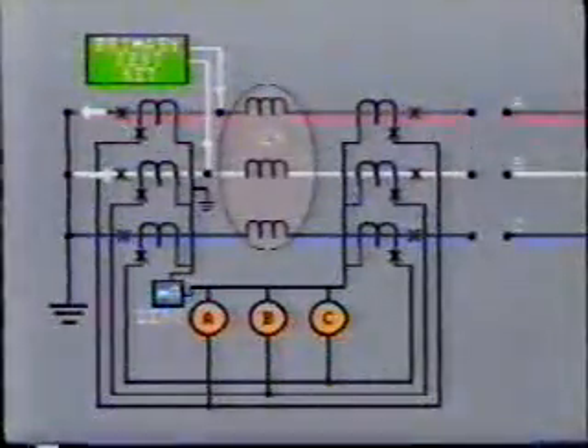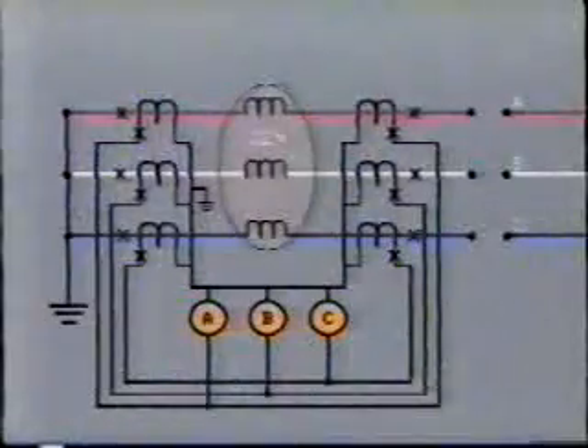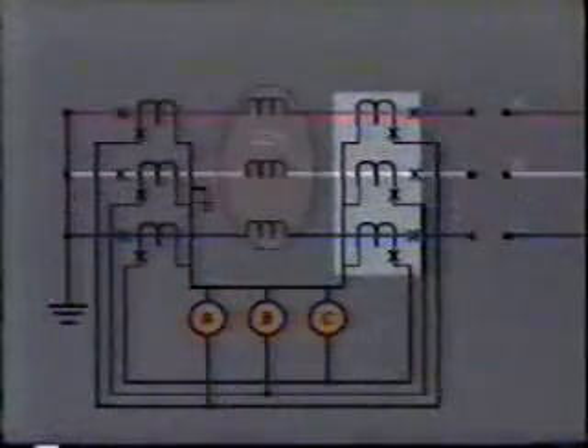To check the balance of these relays, it is necessary to circulate test current between two phases at a time. Remember, the windings are permanently connected together here. This is similar to the test that we performed earlier on the overcurrent relay. A similar set of tests would now be performed on the CTs at the other side of the generator. On the balance test, we would have to place a temporary short between the windings.